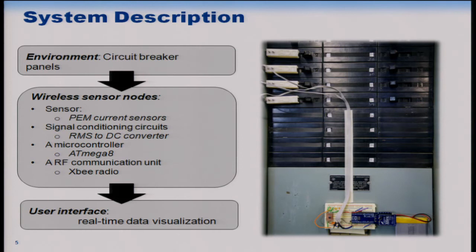The system works as follows: electric current flowing through each breaker generates a certain level of magnetic field, which is picked up by piezo-electromagnetic current sensors. The magnetic field is proportional to how much current flows in each breaker. The system also has a simple signal conditioning circuit to convert the analog differential output from the sensor to a DC voltage, which is then fed into a microcontroller and radio.